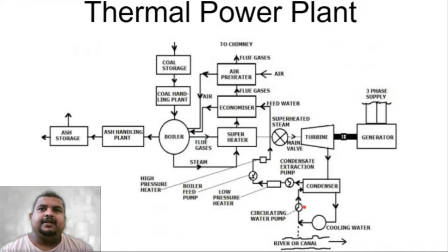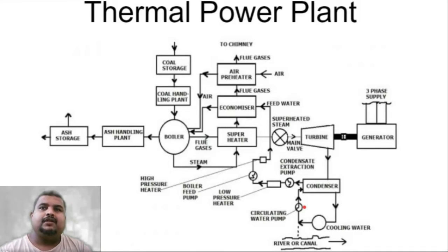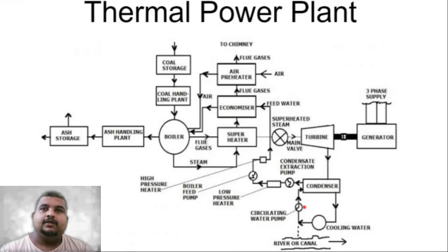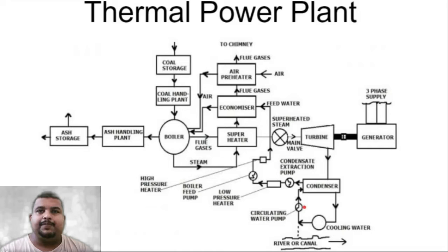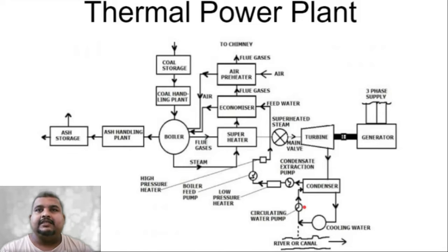There is also a deaerator, which removes dissolved air from the condensate — this is extra information. The boiler feed pump (BFP) is the highest pressure point in the whole system; its outlet pressure is greater than the boiler pressure. After the BFP, the water passes through the high pressure (HP) heater and then the economizer before entering the boiler.